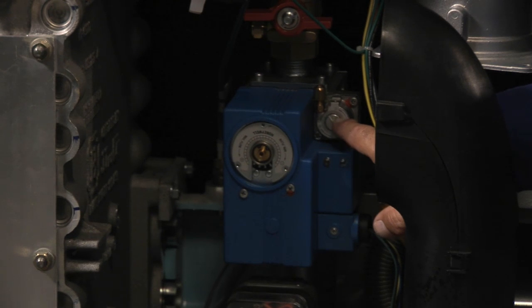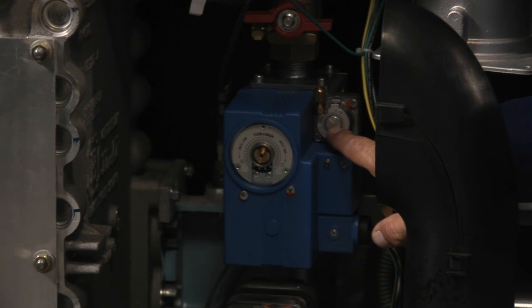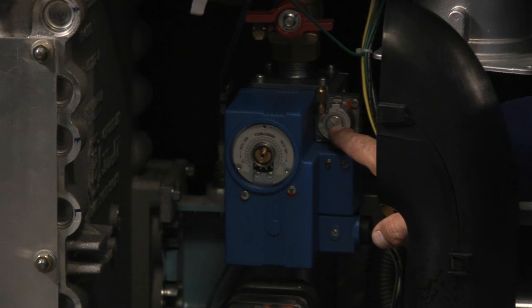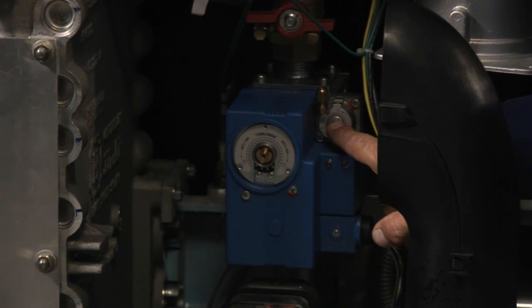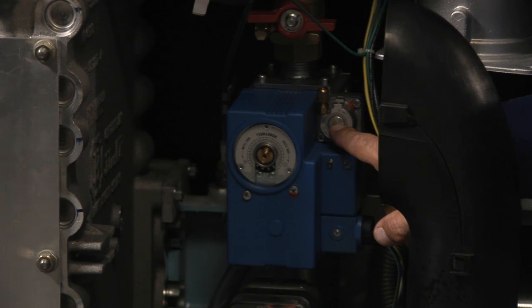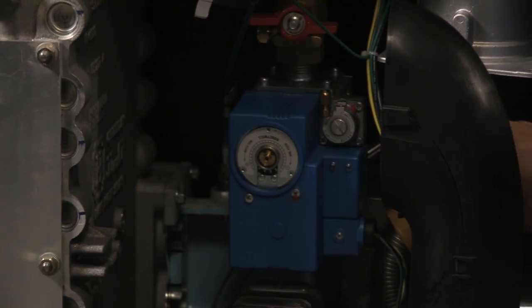Behind this screw, there's an offset setting, and you can set your offset. You're going to refer to the manual to find out what your combustion numbers need to be, but there's an adjustment in here for the offset. That will be done at high fire only.